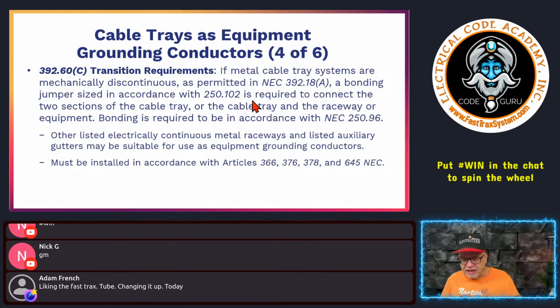Now, other listed electrically continuous metal raceways and listed auxiliary gutters may be suitable for use as equipment grounding conductors. A lot of times you may have an auxiliary gutter, a metal wireway, or other metal raceways that are listed under 250.118(A) to be used as an equipment ground.